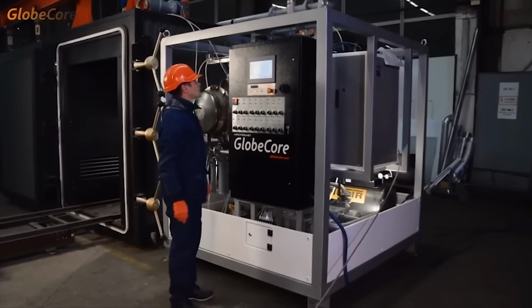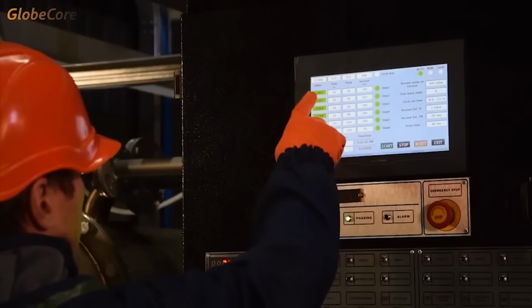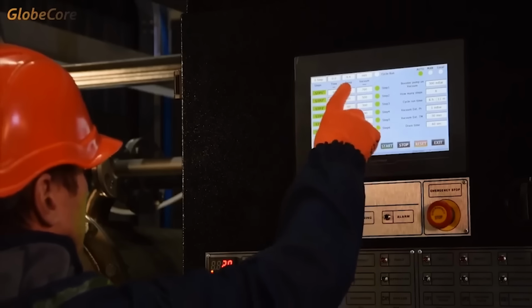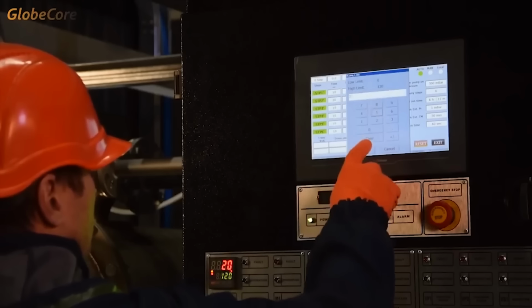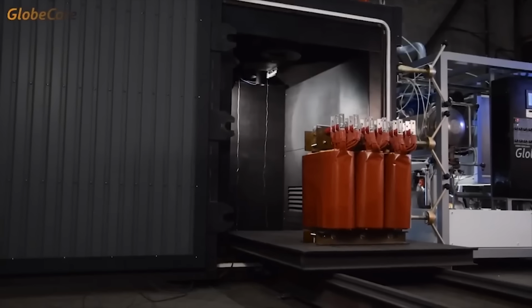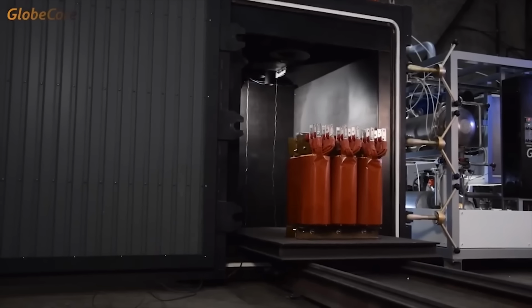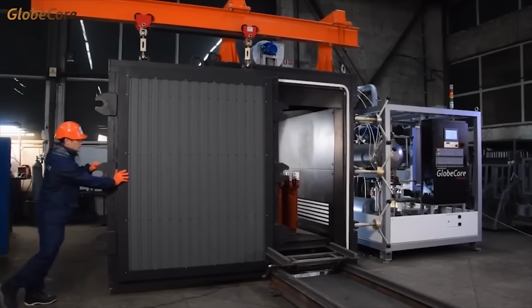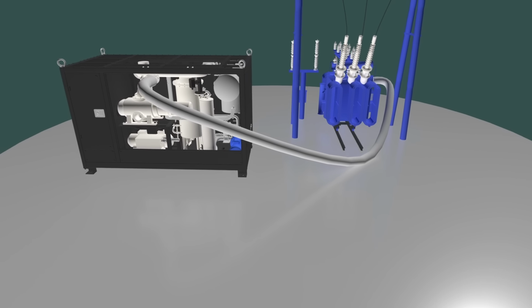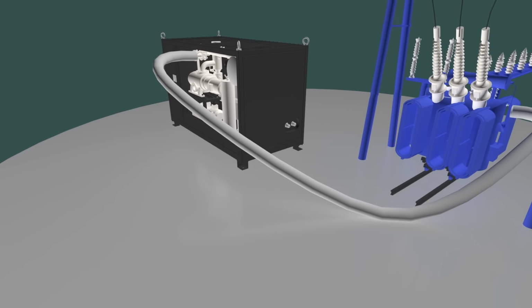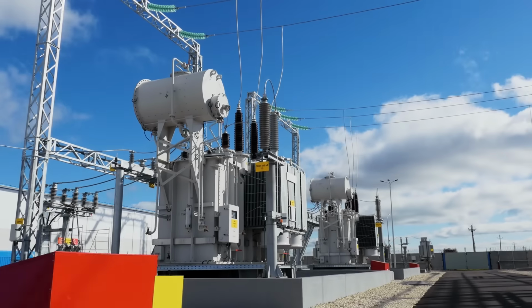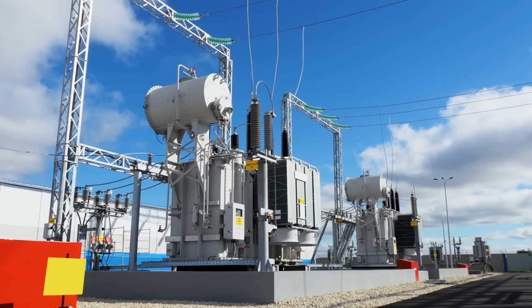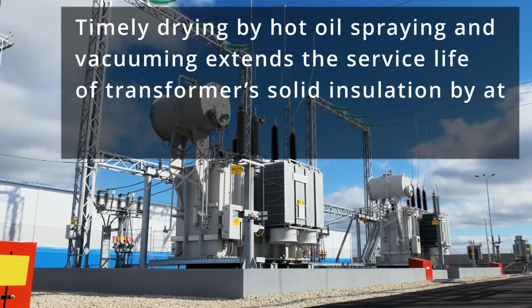In this case, it is recommended to either reinforce the tank before vacuuming, or to extract the windings from the transformer and dry them in a vacuum oven, and then insert them back into the transformer. Timely drying by hot oil spraying and vacuuming increases the dielectric strength and extends the service life of transformers' solid insulation by at least 10 years, and more often than not, by a longer period.